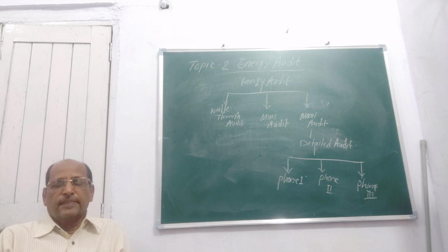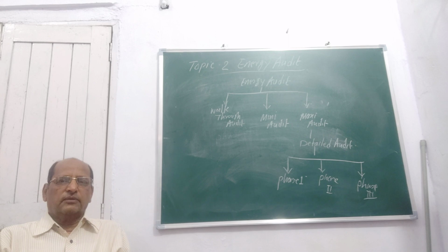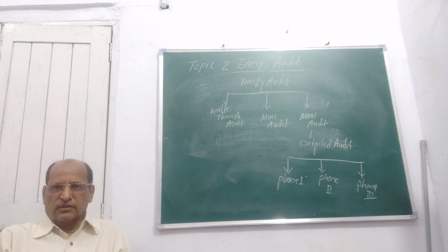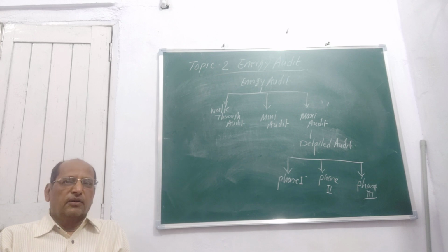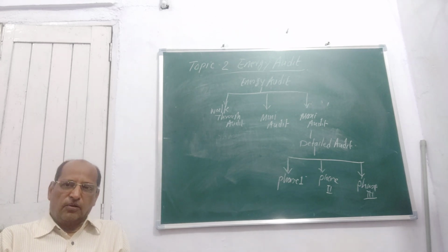You have to make a standard calculation according to the data given, and then the actual performance is observed by running that particular motor for 6 hours, and you measure how much power it consumes in 6 hours, converted into kilowatt hours, that is, units. So you compare the standard consumption according to the theoretical data on the motor specification with the actual data you obtain in performance.